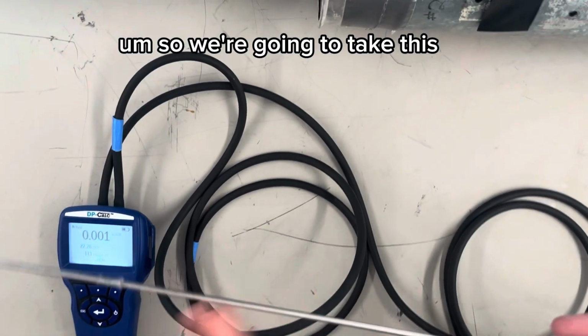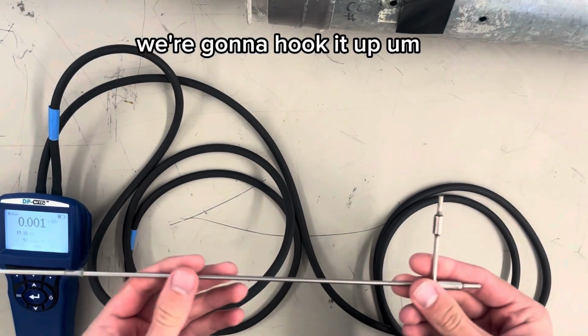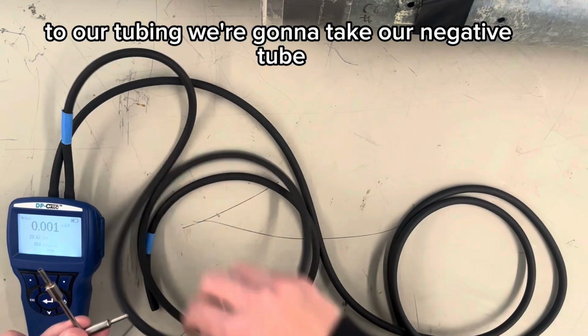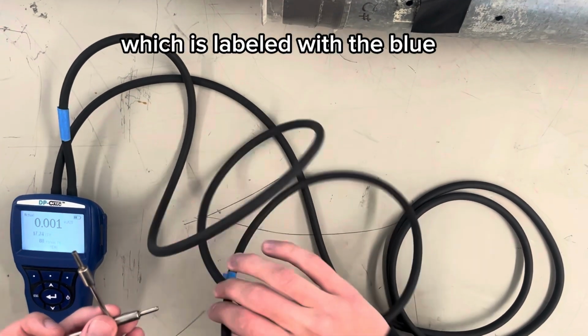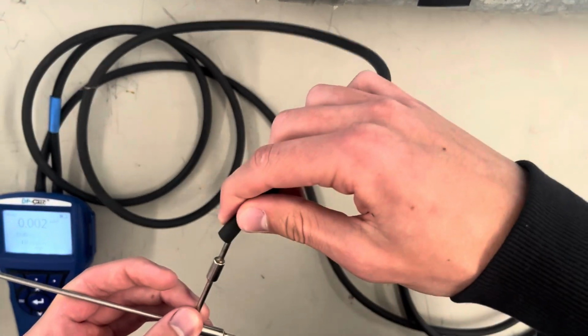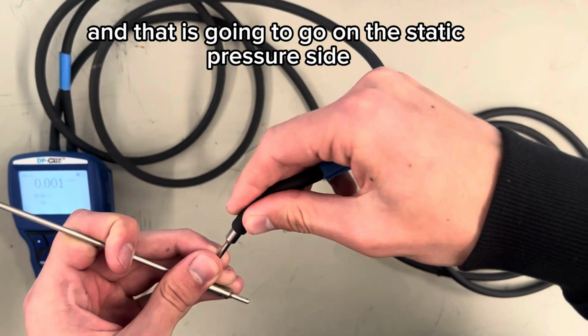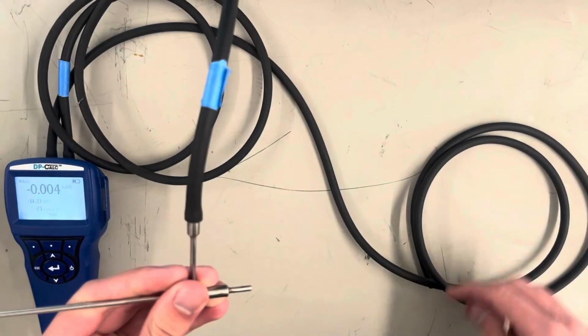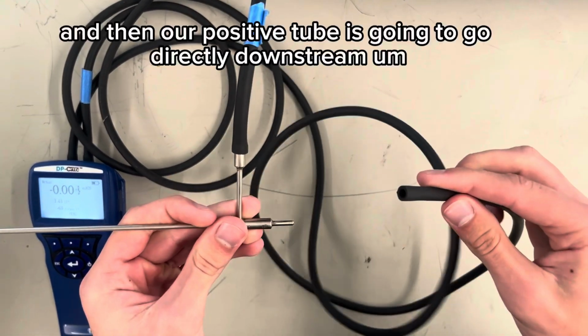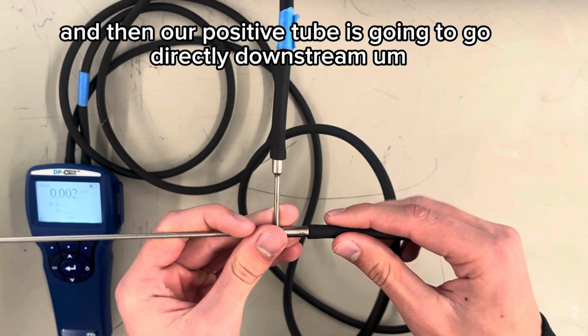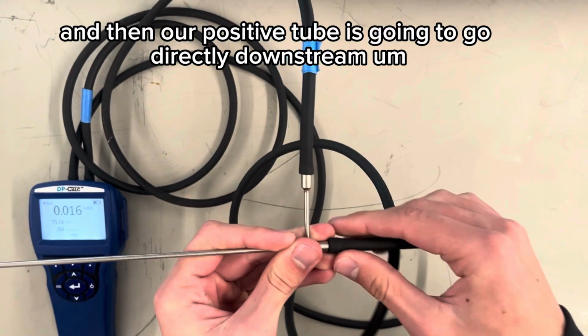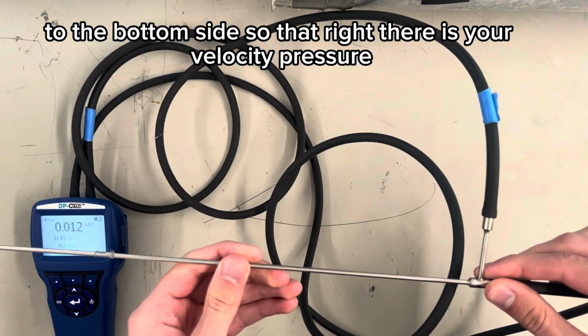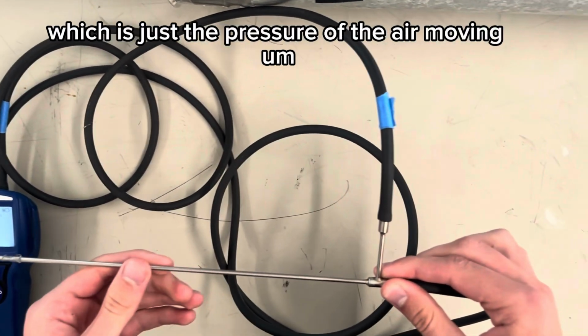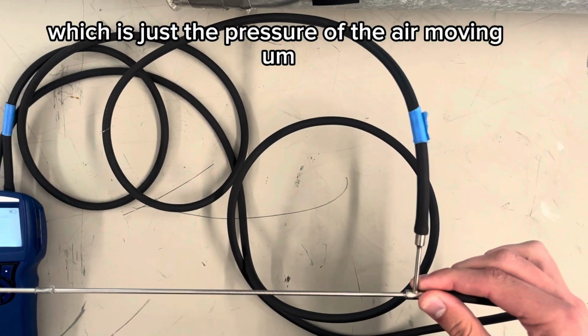So we're going to take this and hook it up to our tubing. We're going to take our negative tube, which is labeled with the blue, and that is going to go on the static pressure side, and our positive tube is going to go directly downstream to the bottom side. So that right there is your velocity pressure, which is just the pressure of the air moving.